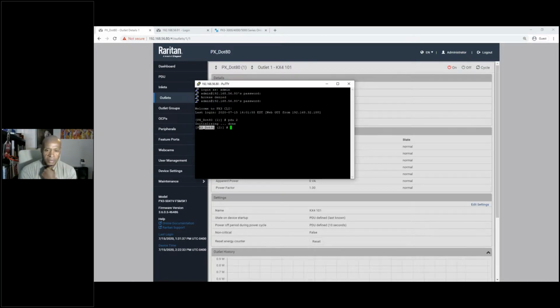They're still going to accumulate power. The active energy sensors and stuff like that will continue to roll. Once the primary unit's back up, everything will get looped back into the master, primary PDU, and you'll notice you have the ability to relink. So if you lose connection on a linked PDU, for instance if a controller dies, as long as you have the same configuration, you can relink a PDU in the web UI. You will have to re-authenticate, but the IP address and host name and stuff like that will remain on the primary unit, so you can relink them.